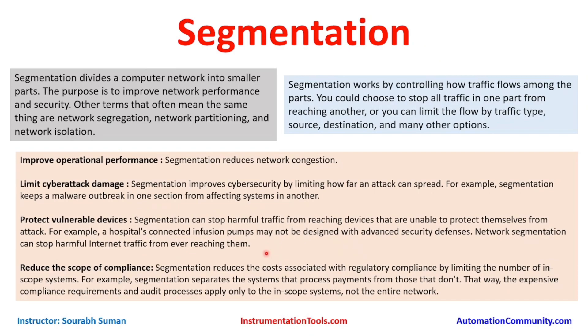Another example is safety instrumentation systems. Those solutions may not be equipped with advanced cybersecurity technologies or have the resources to implement all those cybersecurity solutions. In that case, we can keep all these devices in a safety zone and put boundary protection devices with minimal exchange of data with the upper or other segments. Similarly, vulnerable devices like old or obsolete systems, XP systems, old switches or firewalls can be kept in a different segment with proper boundary protection cybersecurity controls so that all communications going into and out of that segment are inspected, untrusted traffic flagged, and monitored at all times. That will help you protect your vulnerable devices.